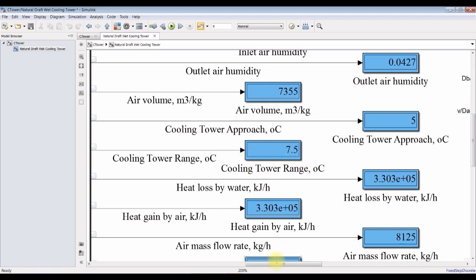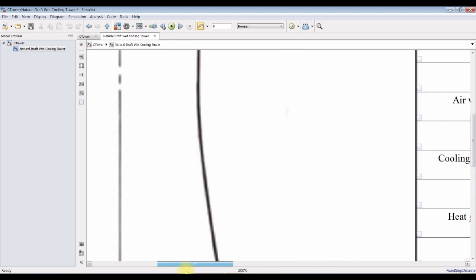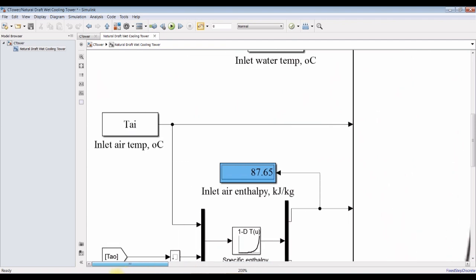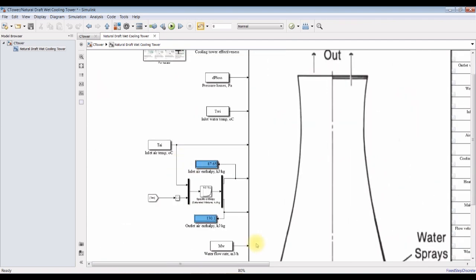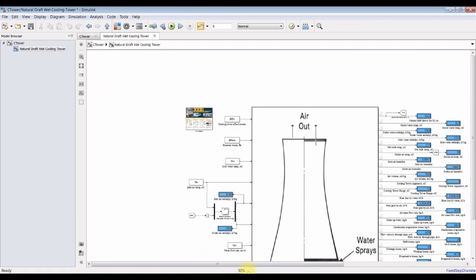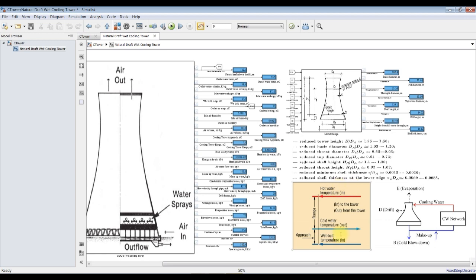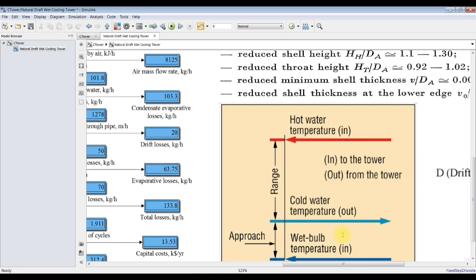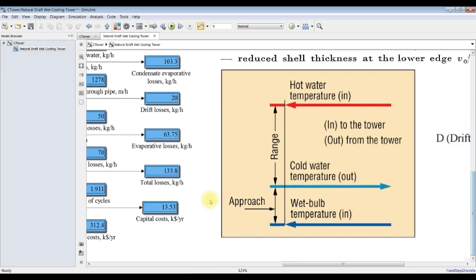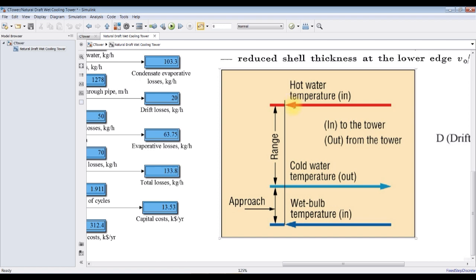And you can define cooling tower range and approach by this figure. This is the approach, the difference between wet bulb and cooling water outlet. And the range is the difference between cooling water outlet and hot water inlet temperature. That's the range.